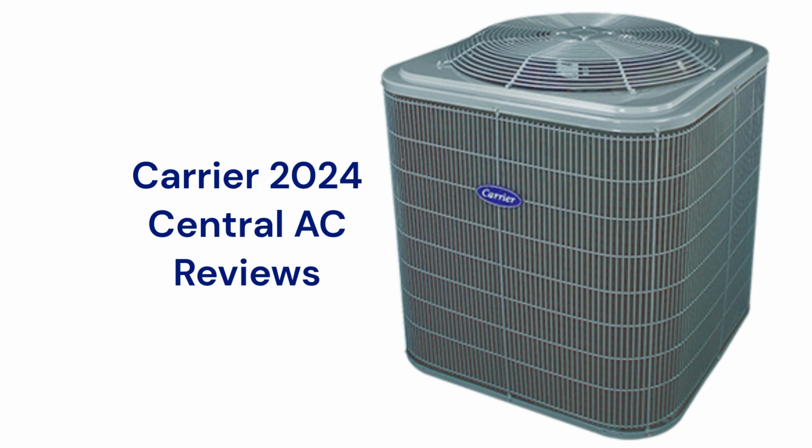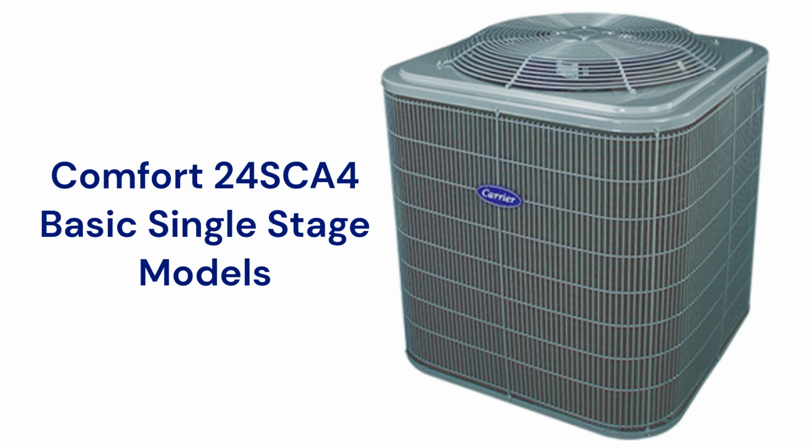This brand is made in Mexico and is available in the USA and Canada through their authorized dealer network. The Comfort 24 SCA4 air conditioners are basic units with a 16 SEER efficiency. They have a durable powder coat finish but only a wire coil guard, which is not very effective at protecting the fins of the condensing unit from mechanical damage from debris thrown by a lawnmower or from hail.